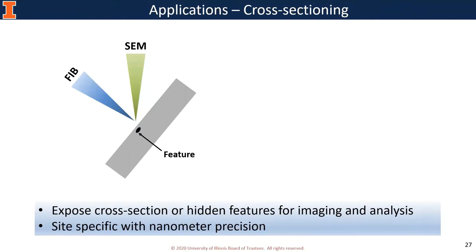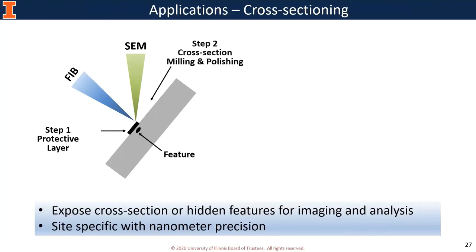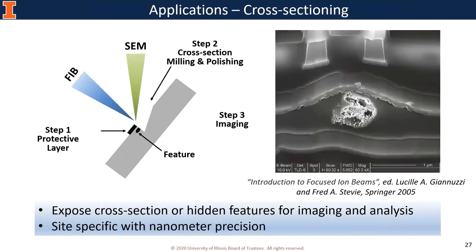The most popular application of FIB is cross-sectioning. Through cross-sectioning, features hidden underneath the sample surface can be revealed, imaged, and analyzed. Compared with conventional cross-sectioning methods, FIB allows site-specific cross-sectioning which cannot be done with conventional methods. Cross-sectioning usually starts with depositing a protective layer to the sample surface using e-beam or ion beam. Then we mill to expose the subsurface using a cross-sectioning pattern with the ion beam. After that, we polish or clean the cross-section surface with a smaller ion beam, and then image or analyze it.